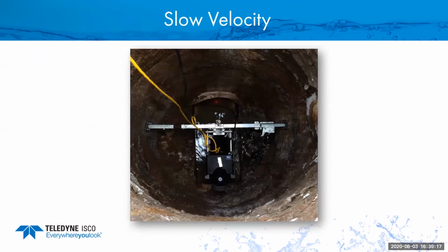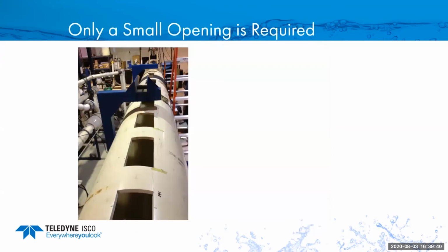Here's an application where you can see the laser beam hitting the water. In this case, you can see the surface looks like glass. It's barely moving. Very, very challenging. A non-laser technology would not work so well here because you need some surface velocity for a radar unit to work. The laser is able to read that.